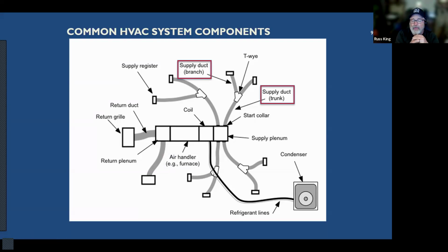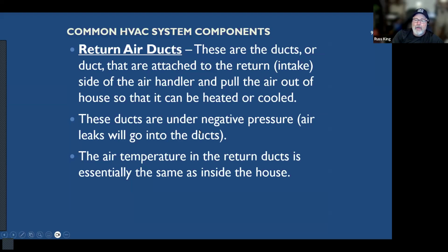But a lot of times what they do in houses that have basements is the furnace will be in the basement, an upflow furnace, and there'll be a long rectangular trunk that runs the length of the house. Okay. And then they'll have branches coming off of that to go into each room. Same thing. Trunk splits, branches terminate. Okay. Trunks and branches. And then return air ducts.